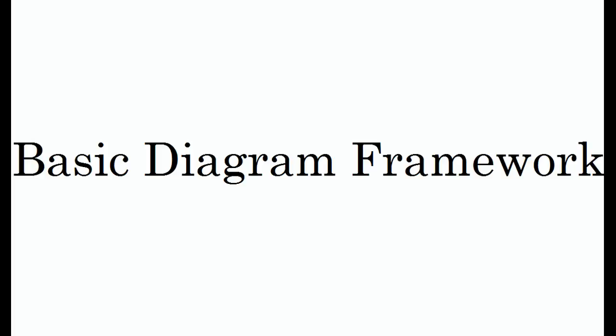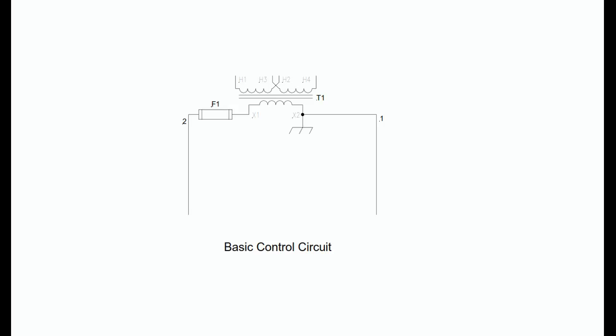Beginning with the control transformer, we add a protective fuse on the left side. As mentioned earlier, in many cases the fuse is part of the transformer itself. From the transformer-fuse combination, horizontal lines are drawn to both sides and then drawn vertically down the page as shown in figure 1-18. These vertical lines are called power rails or simply rails or uprights.